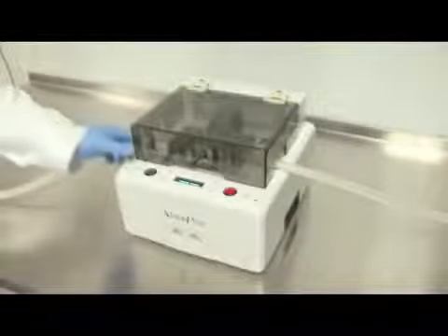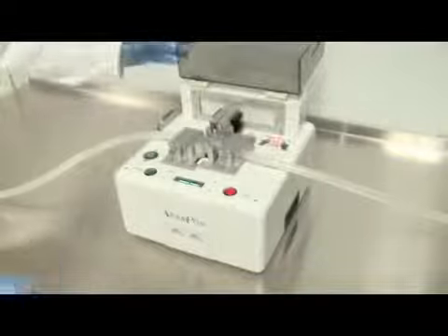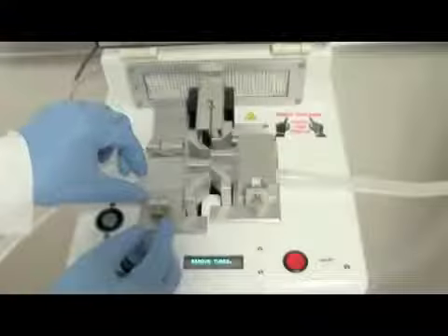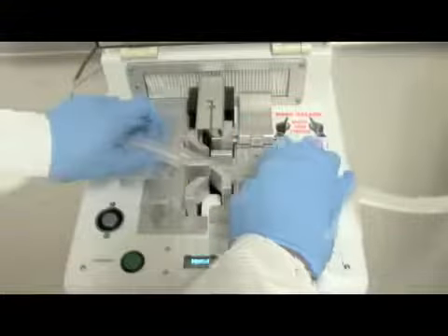The device repositions and aligns the tubing pathways to make the connection, withdraws the blade, and welds the two ends together, re-establishing a sterile fluid pathway. After the cycle is completed, the cover is lifted, the cutoffs are removed and discarded, and the reconnected tubing is removed, producing a validated sterile welded pathway without the use of expensive aseptic connectors.